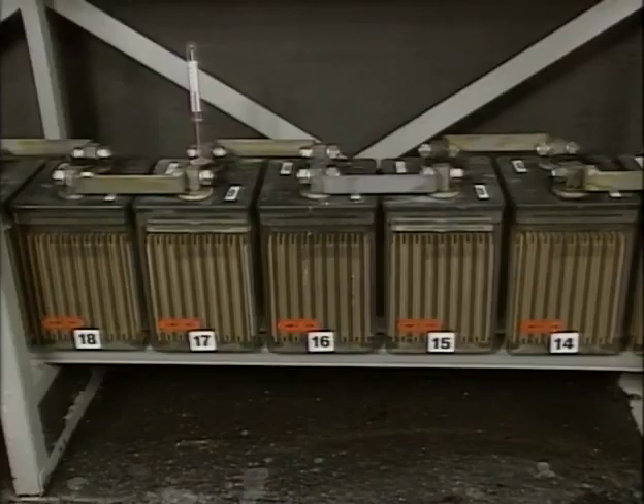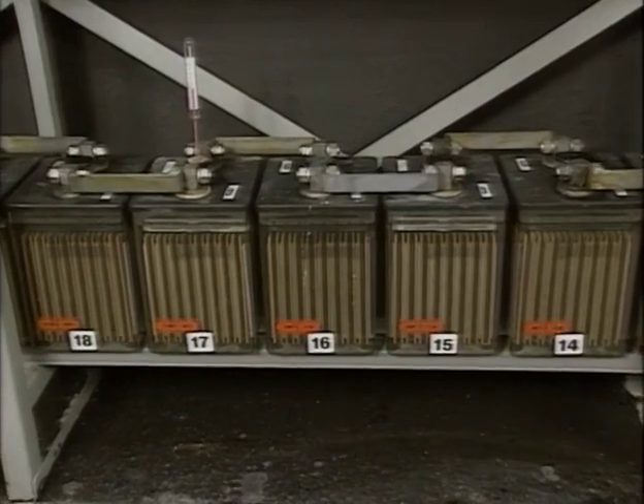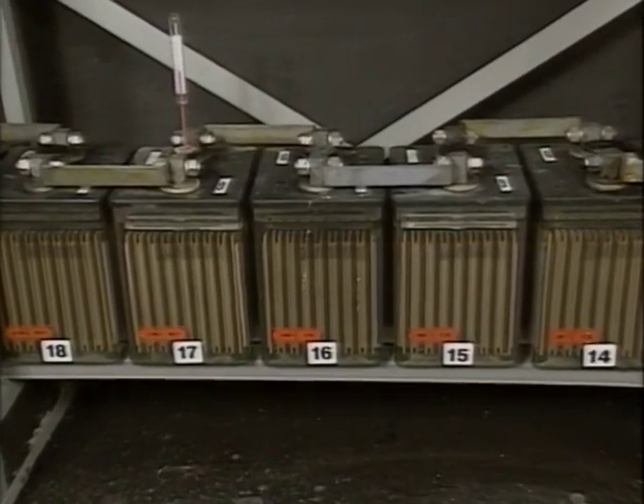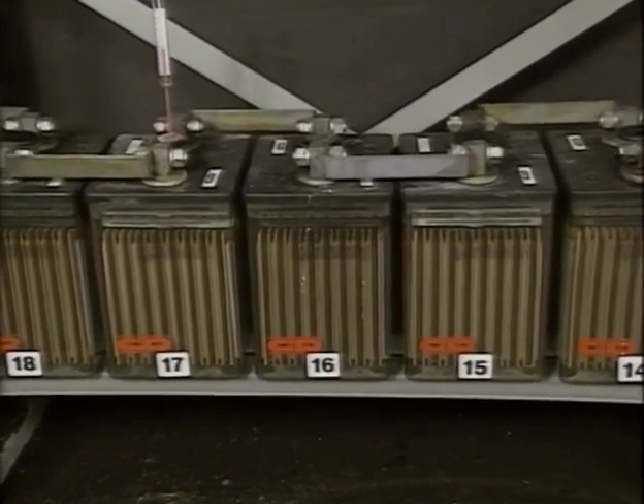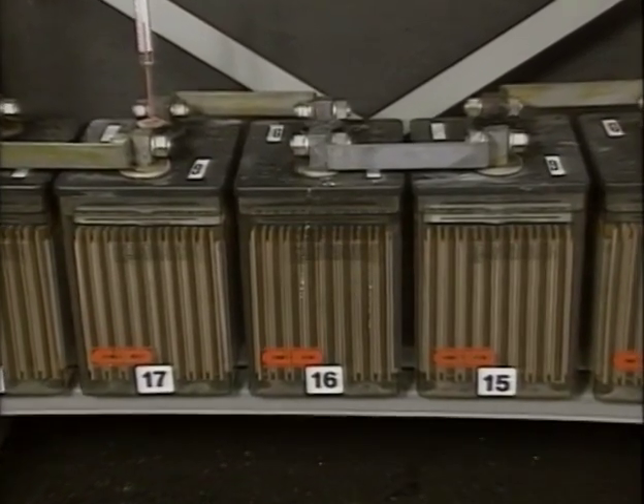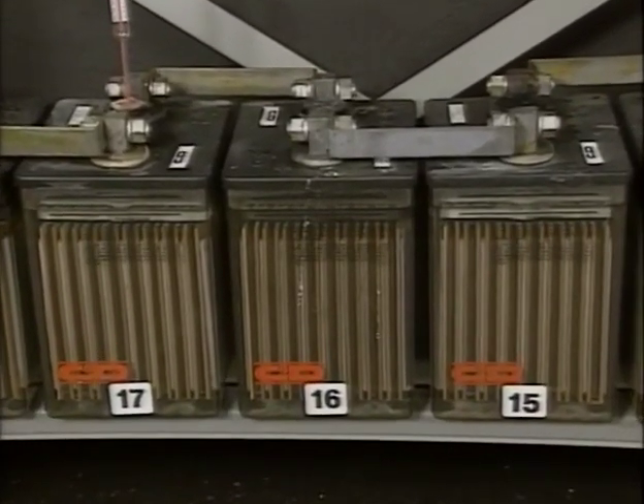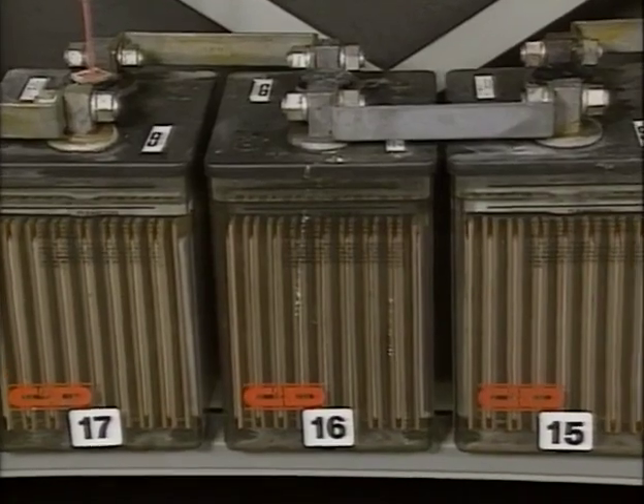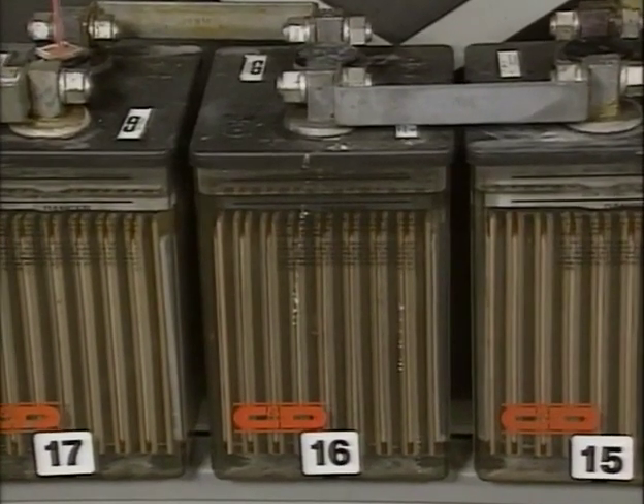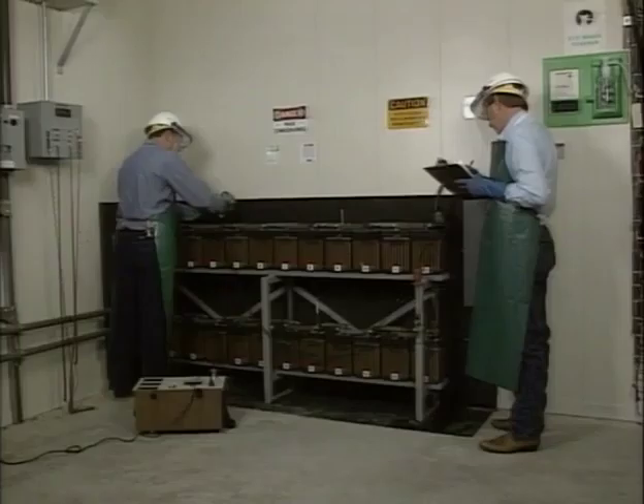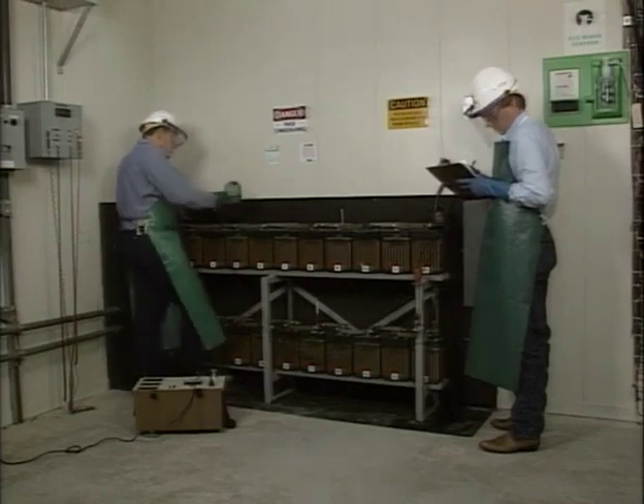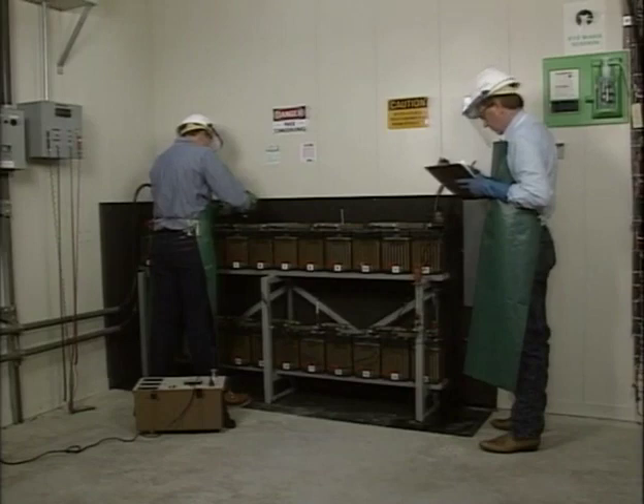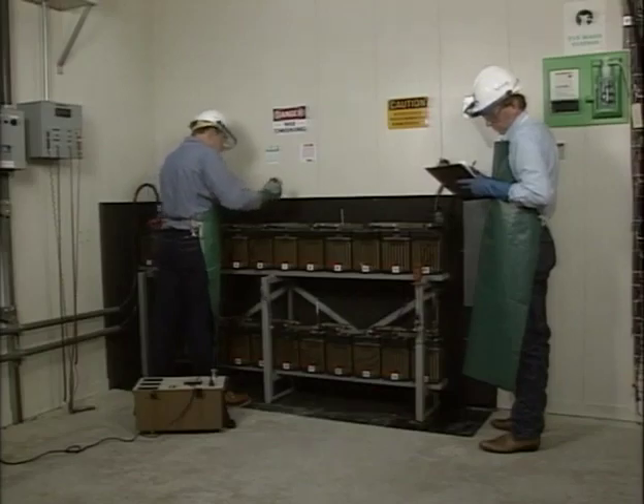It's important to know that an integrity test places a high current stress on all the cells. If a cell is mechanically defective, the stress of an integrity test could cause the cell to explode. For this reason, the visual inspection and other preliminary checks are very important. Another test, called an impedance test, may also be useful in identifying defective cells before an integrity test is done. The impedance test will be shown later in this program.